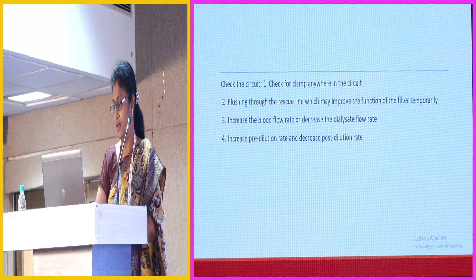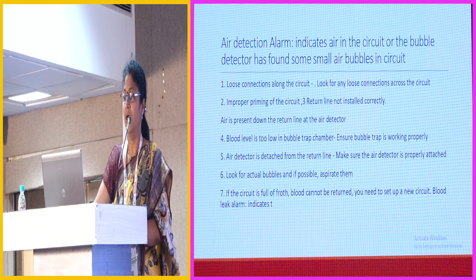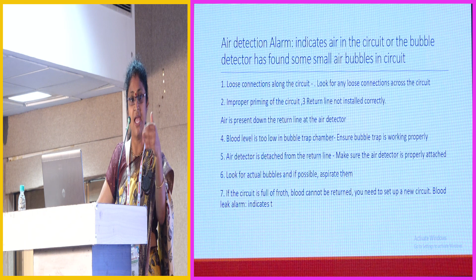Air detection alarm is something like in regular HD alarm. It indicates air in the circuit or some small air bubbles in the circuit. I want to highlight that we all know there may be many causes for air in the circuit, but the most important thing is to fill the blood air trap chamber to the mark that is specified on the machine. Most of the time we don't fill it to that mark. So the machine starts to recognize air in that bubble trap chamber and gives an alarm. So that is very important.